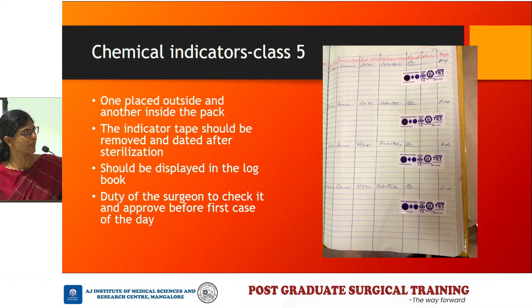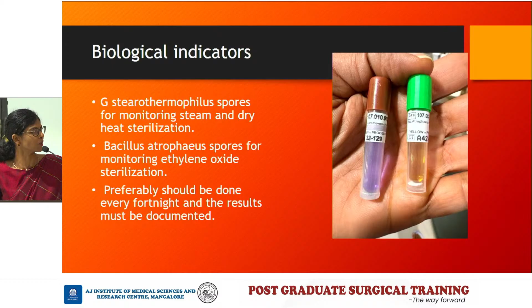Biological indicators are used both for autoclave and for ETO sterilization. Now these use the spores of Bacillus basically, and nowadays you have these rapid readout ones where there's a color change immediately and you know that the spores have been killed. So this has to be done every fortnight, and the results must be documented. This gives you a better idea that the sterilization apparatus is working correctly.